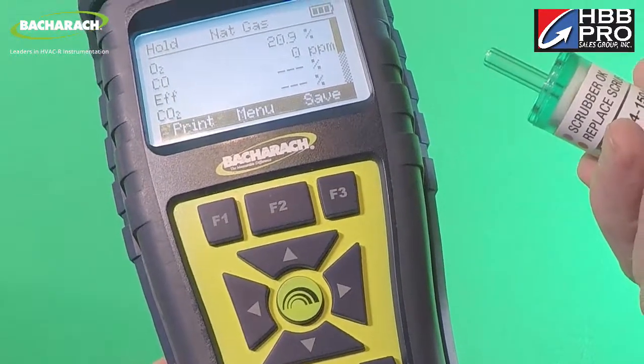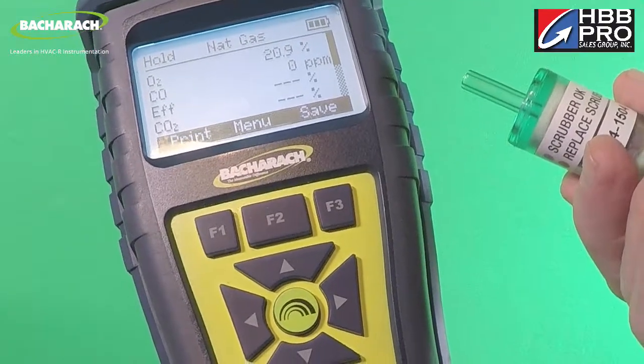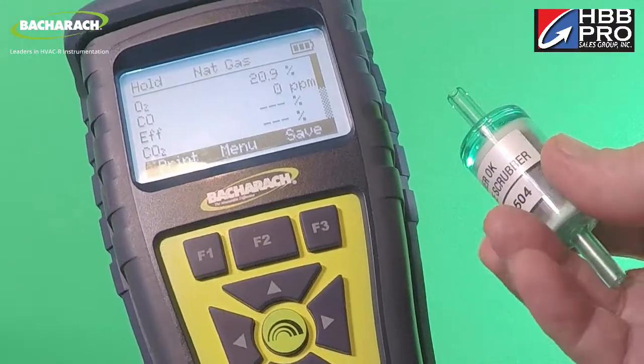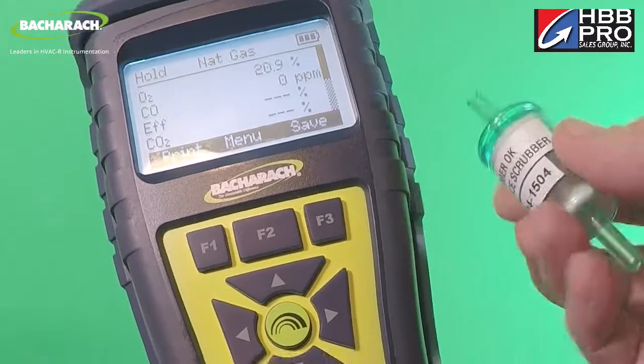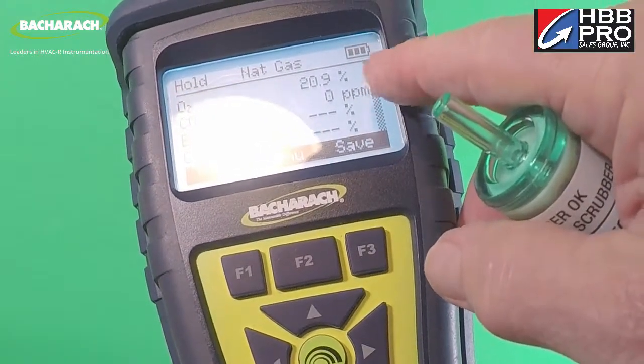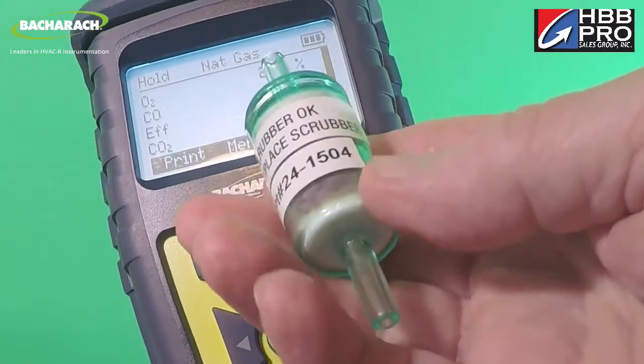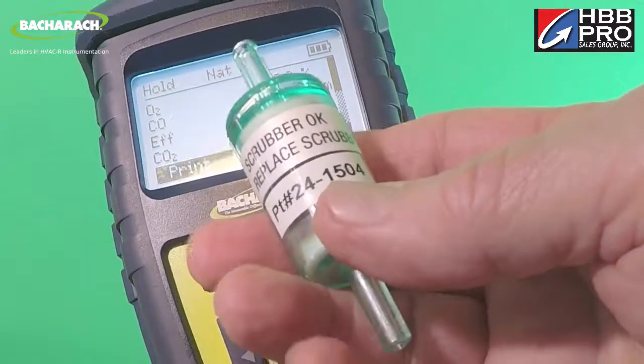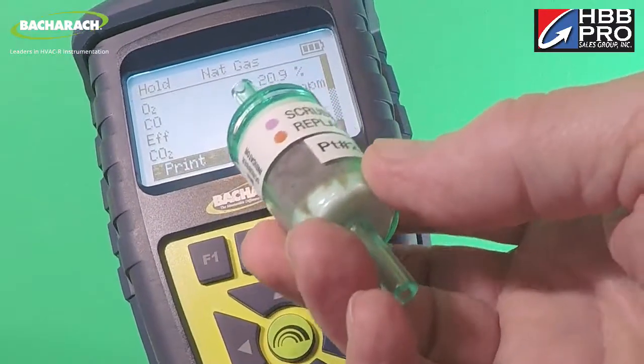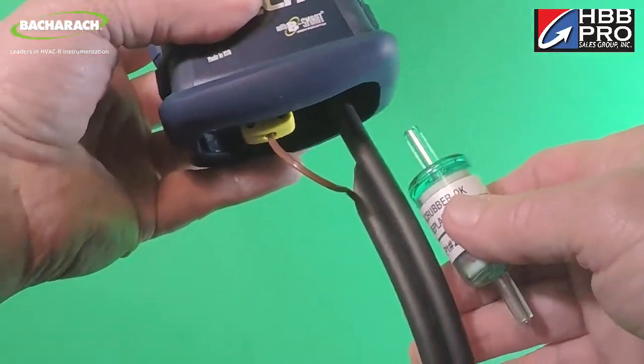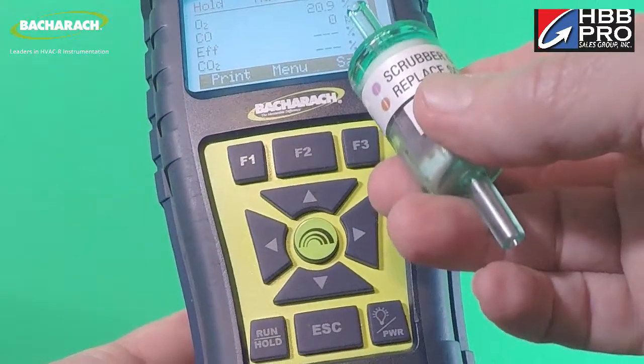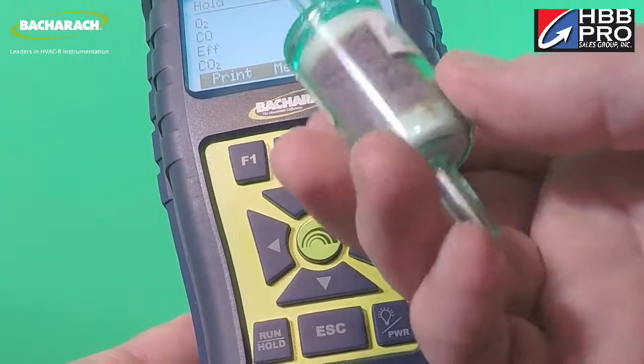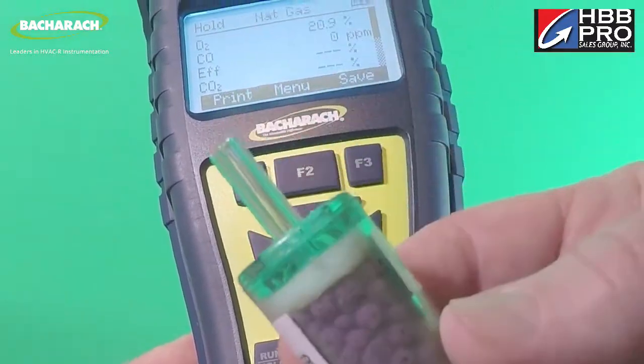So a couple of things to keep in mind. One is that all carbon monoxide sensors are cross-sensitive to NOx. One difference between the InTech and the Insight Plus is that the CO sensor in the InTech is not NOx filtered. As a result, you'll get a little bit higher carbon monoxide readings with that non-filtered sensor. You may wish to consider adding an external NOx filter just to make those carbon monoxide readings more accurate. This is what the filter looks like. You simply cut out a chunk of the hose and probe assembly and slip this in place. One advantage of having an external filter is that you can visually monitor how contaminated the filter beads are and replace it when necessary.